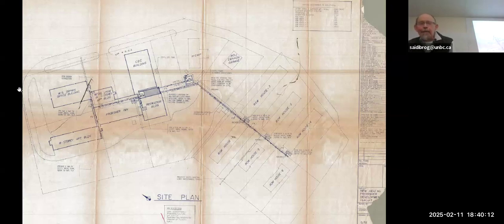If you look up here, there's a table of heating requirements in the top right corner. You can't read them, but they total 14 million BTU per hour. And I excuse the imperial units, but for some reason, my industry has never properly converted to metric because it's based in the United States and they're behind the times. So you'll have to bear with it. So with the known load of the buildings at 14 million BTU, a boiler plant with an input of 17 million BTU was required, allowing it to meet the design load operating at 80% efficiency.